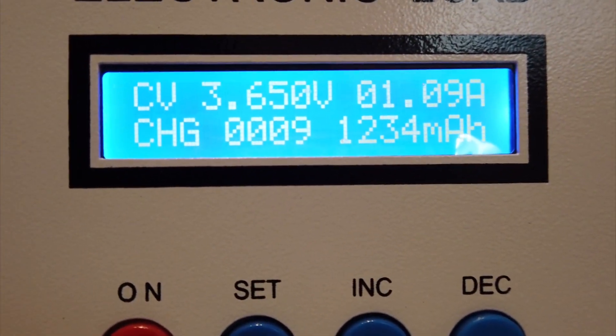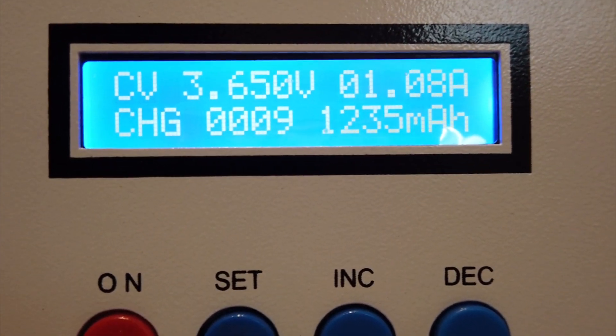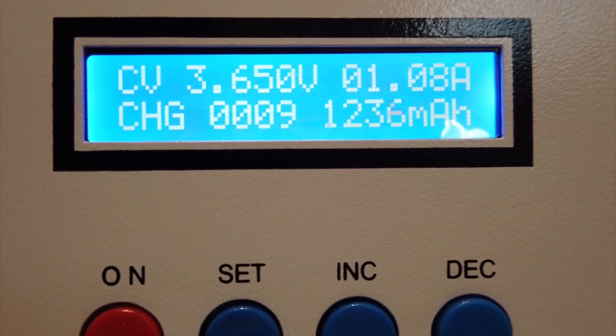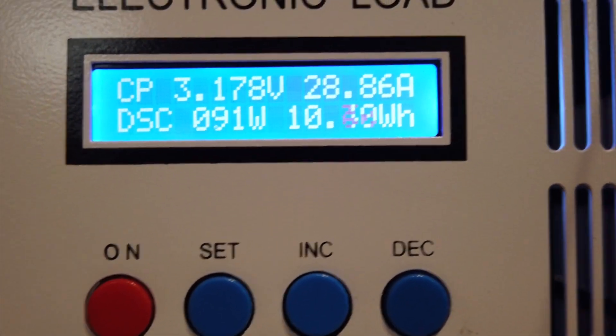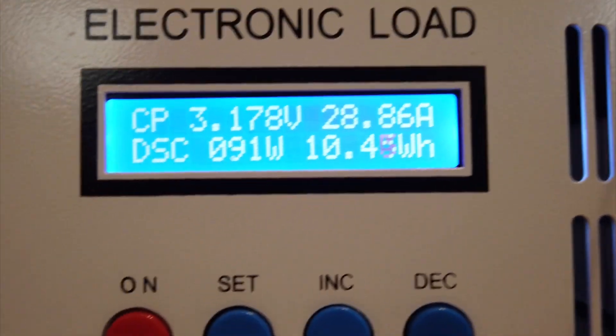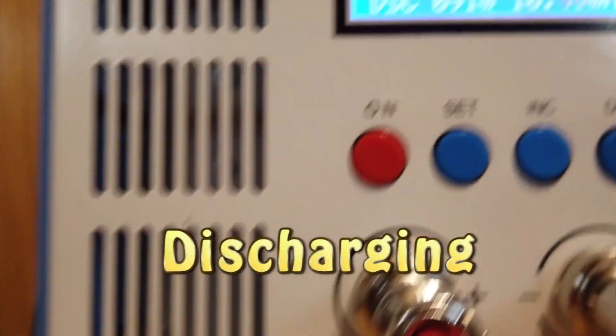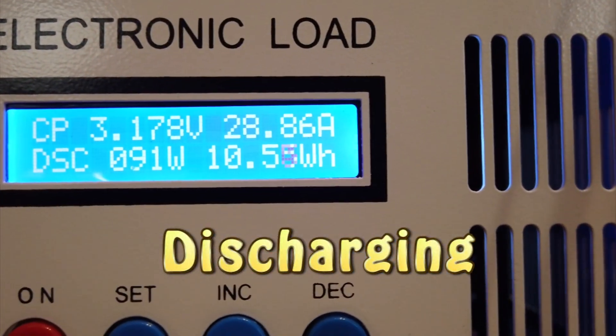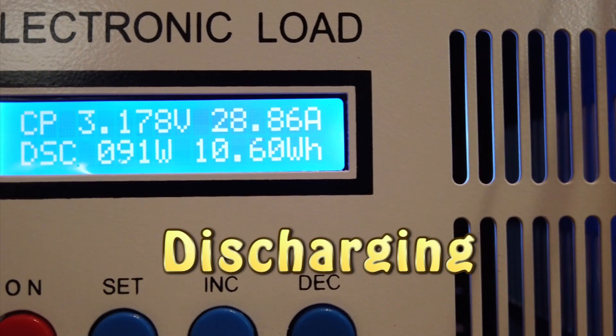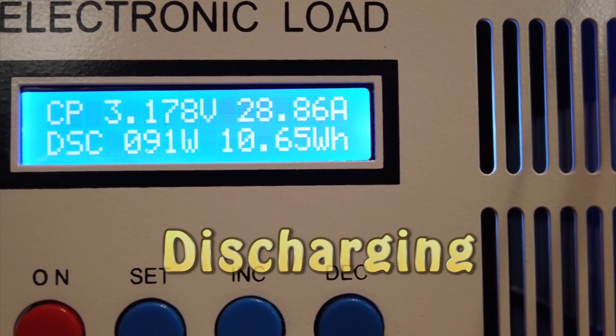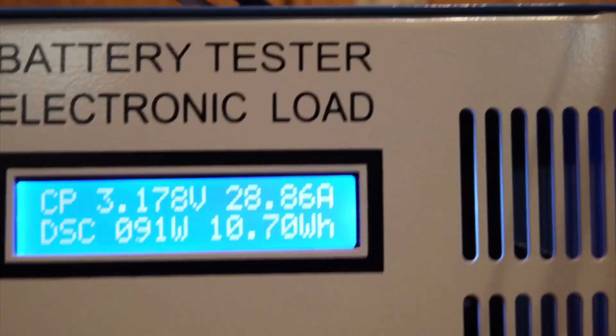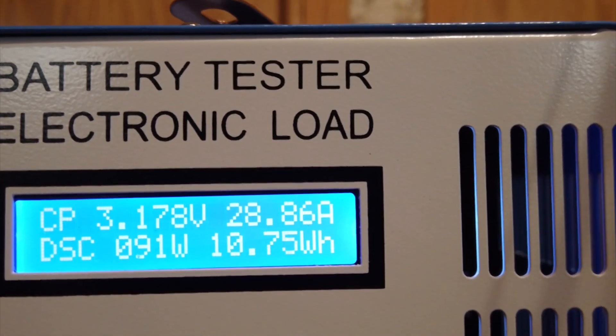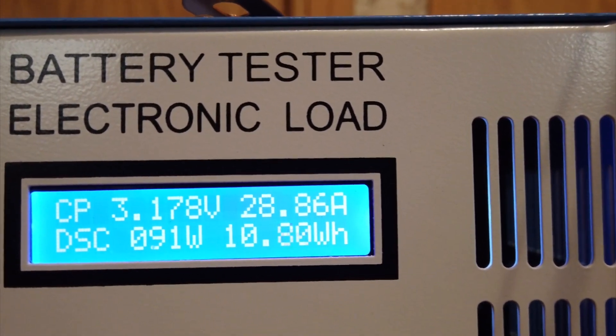You can kind of see it clicking down because at 3.65 at one amp, it's going to be between 95 and 99 percent fully charged. And right now battery number 15, which is on the Z Tech, is discharging at 28.86 amps. And it's okay, it'll take a while for this to get done. Now this...